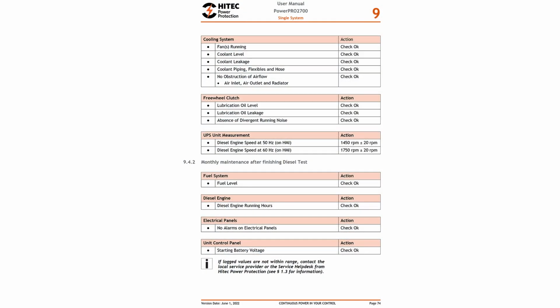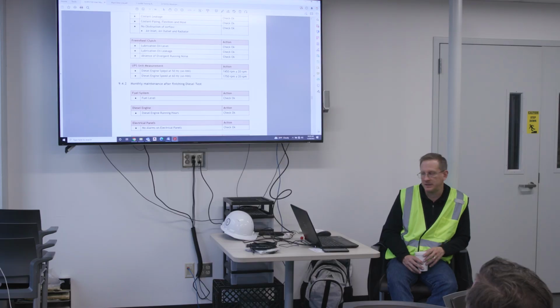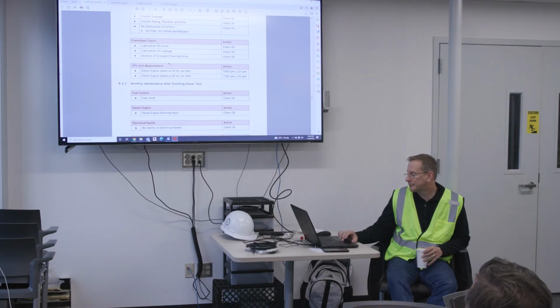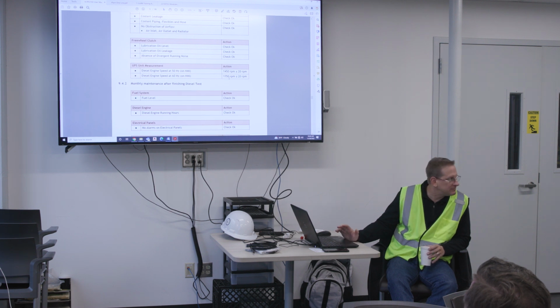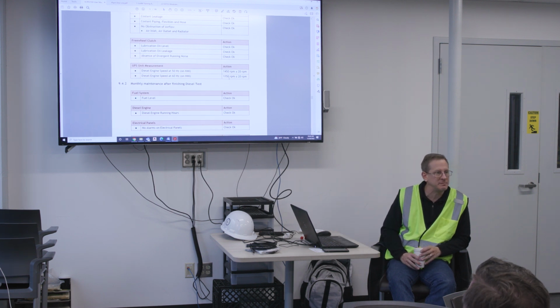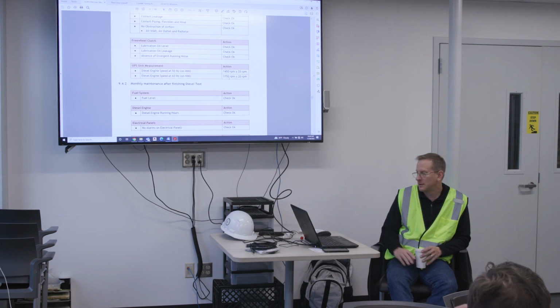In the monthlies, this is where you'd want to run a diesel test. Start your diesel, let it run, and make sure it's running at the proper idle speed—expect approximately 1750 RPM for idle speed. That's something you'd do on a monthly basis.